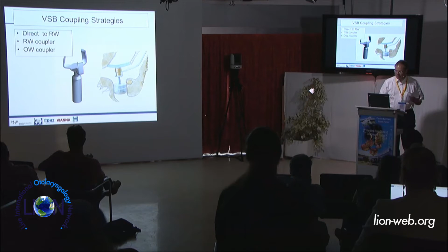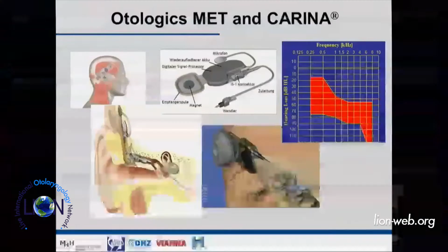When we need more power, then you basically need two points of fixation. That is given with the Otologics middle ear transducer and the totally implantable version called Carina. The principle is a transducer, which is basically fixed here at the rim of the mastoid, and the tip, which is moving, is connected to the incus body. That is the initial installation. And you see they can serve patients that have more pronounced inner ear hearing loss, where the sensory component is larger, so it's up to severe hearing loss. That's possible. The fully implantable version also has an implantable microphone and an implantable battery package.